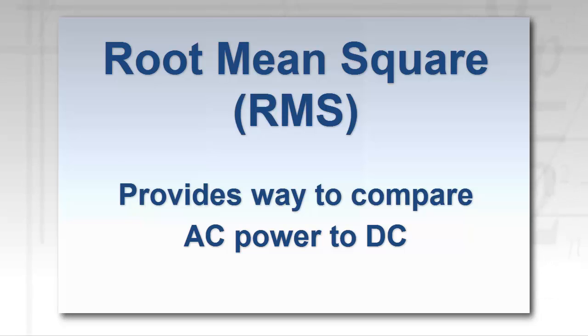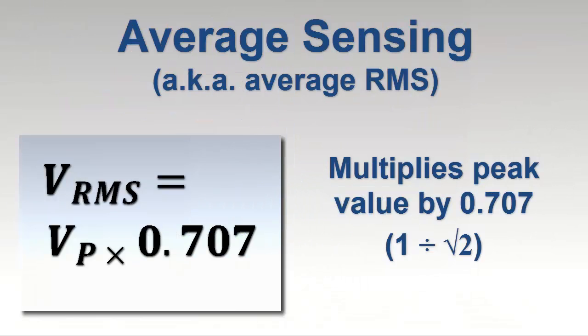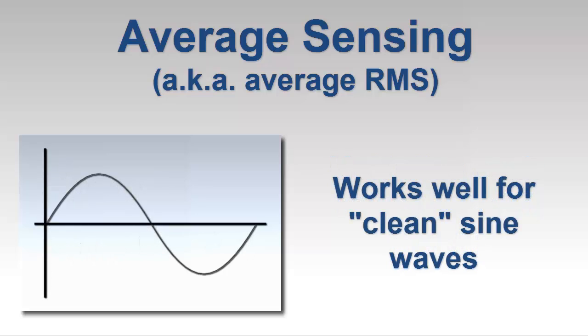Some low-end instruments employ a technique known as average sensing, sometimes referred to as average RMS. This entails multiplying the peak AC voltage or current by 1 over the square root of 2, or 0.707. For electrical systems where the AC cycle is sinusoidal with undistorted waveforms, this can produce accurate and reliable results.